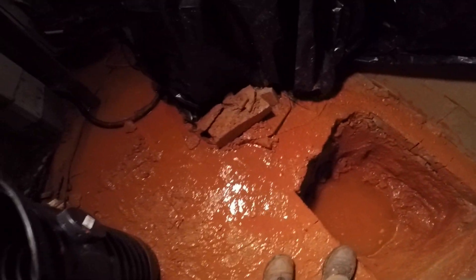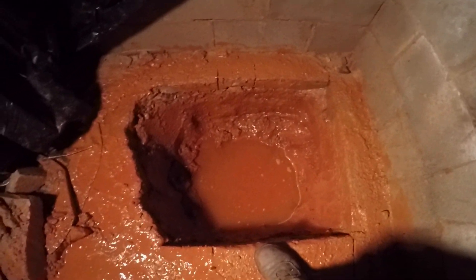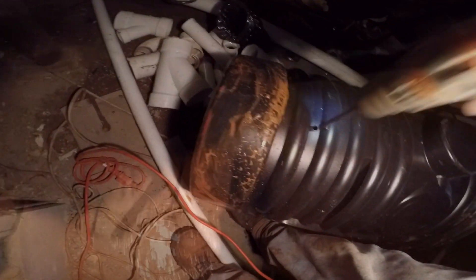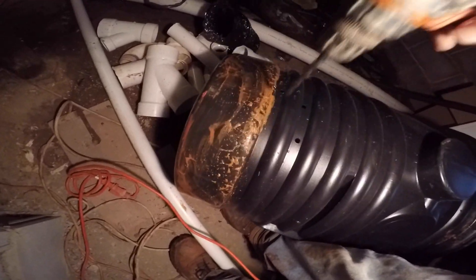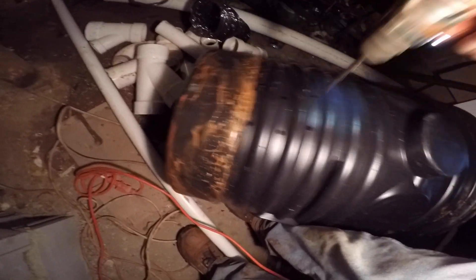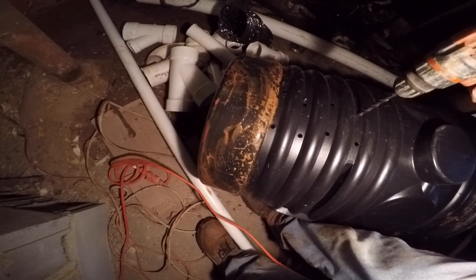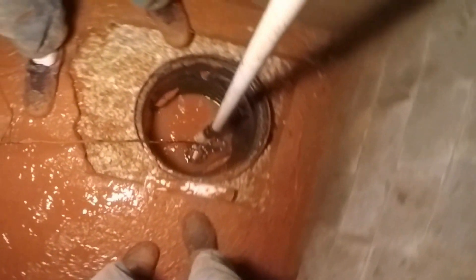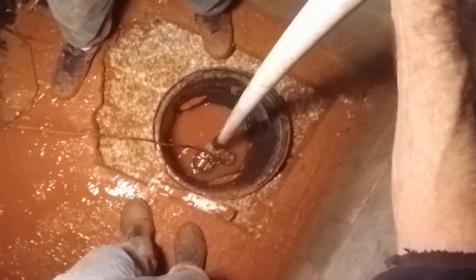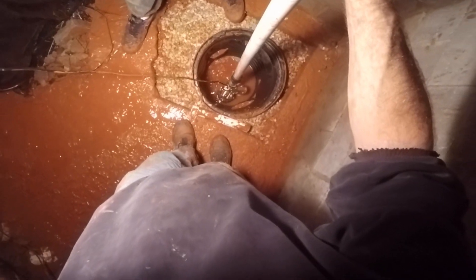When you're working in a muddy area in the water — you can see it's just pure mud here — this is all going to get rinsed off and then we'll pour the concrete back, flushed to the floor. It's really important that you perforate your pit because that's the collection point. There is no pipe here — we're just collecting the water that's under the floor, because this is a very small area, maybe only six by six. After we surrounded the pit with gravel, you can see the water moving through the gravel into the sump basin. This is perfect.